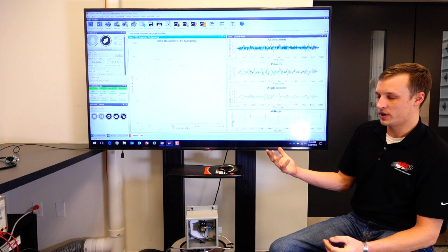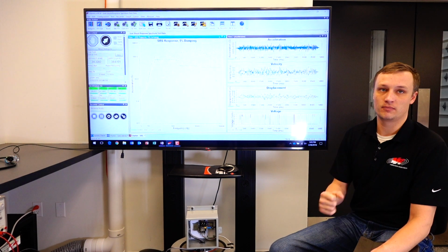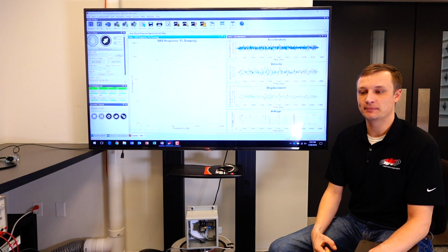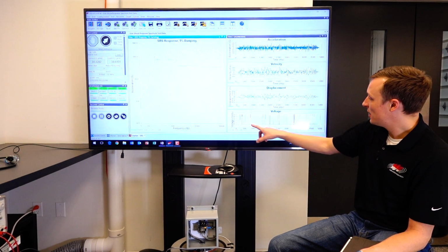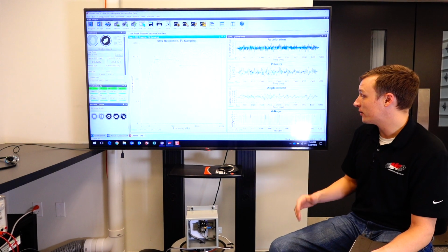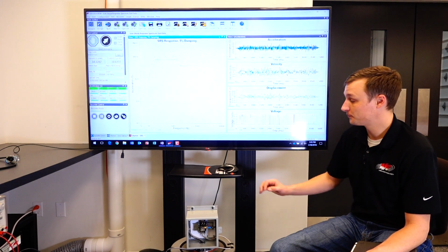So now my recording is completed. I haven't generated a file or a chatter table, but I can visually see that I have a lot of chatter events occurring in that voltage versus time graph.